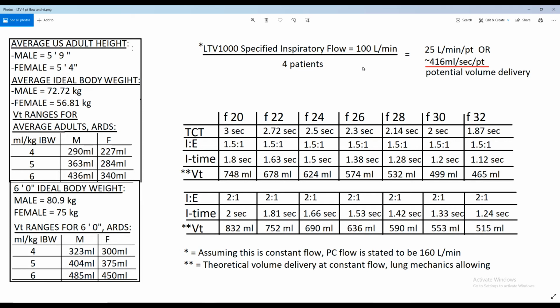Well, here's my modifiers I'm going to throw on there. This 100 liters per minute, if we look at the asterisk, I'm assuming that this is constant flow, because right below that in the specifications it said its pressure control flow was 160 liters per minute. But we know that pressure control doesn't have constant flow, so it would be very difficult to do these calculations. So these calculations are based on the idea that the LTV can comfortably deliver a constant flow of 100 liters per minute during the inspiratory cycle. I hope everybody understood that, but it gets kind of confusing.